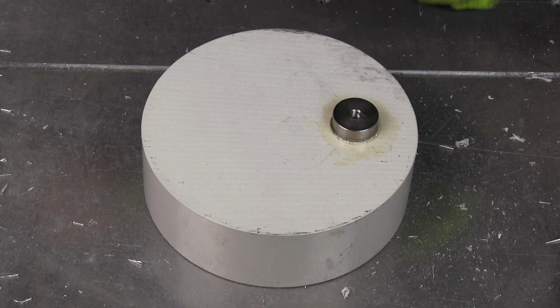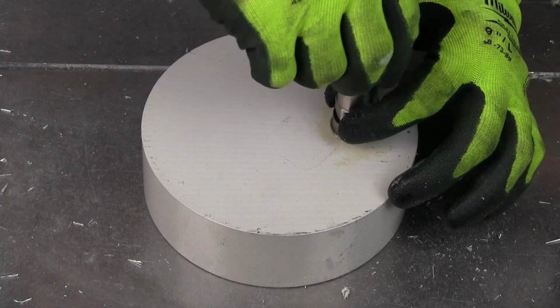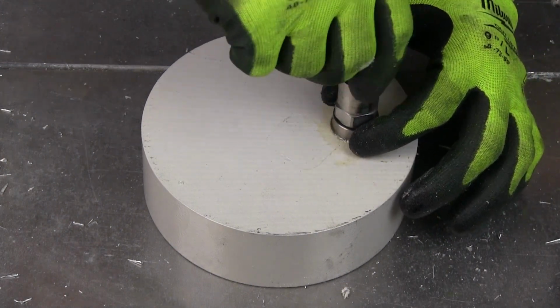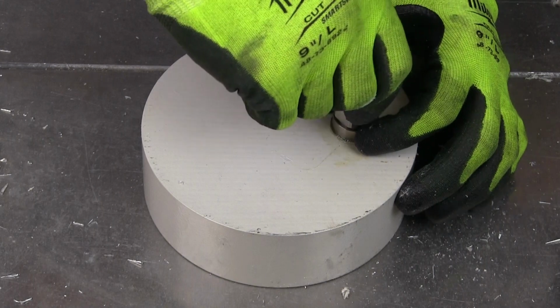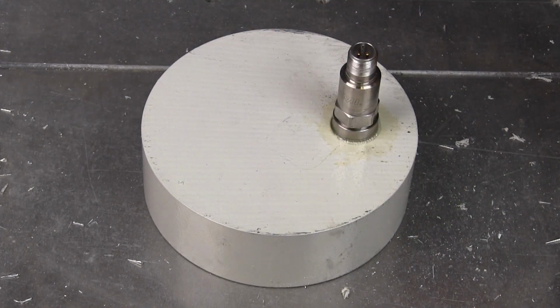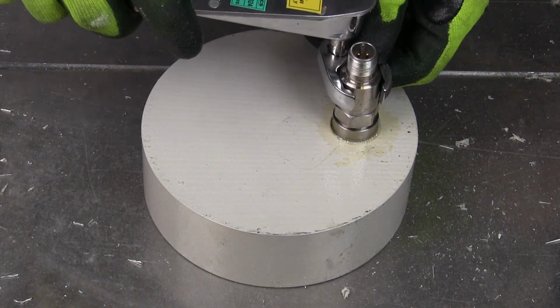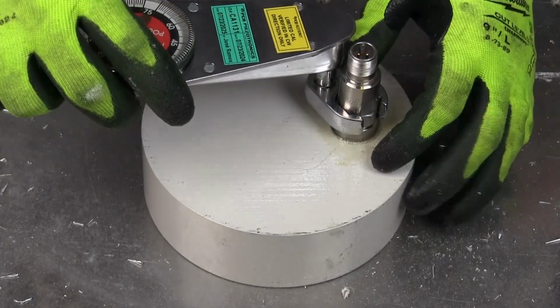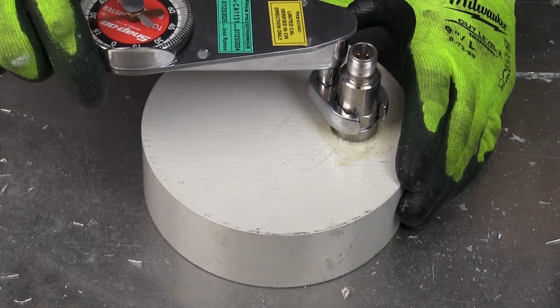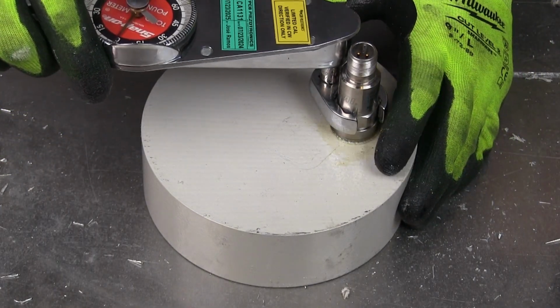Finally, the stud is removed from the center of the adhesive mounting pad, installed in the accelerometer, brass tip in first, and then the accelerometer is stud mounted. 2 to 5 foot-pounds of torque or 3 to 7 Newton meters of torque are required.